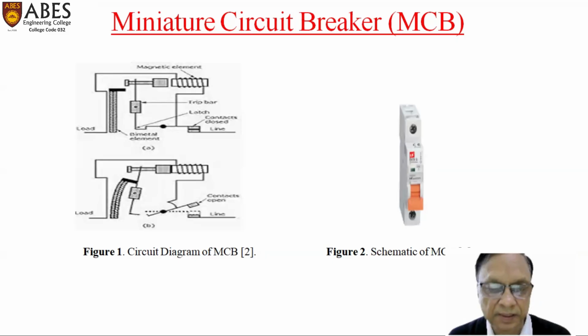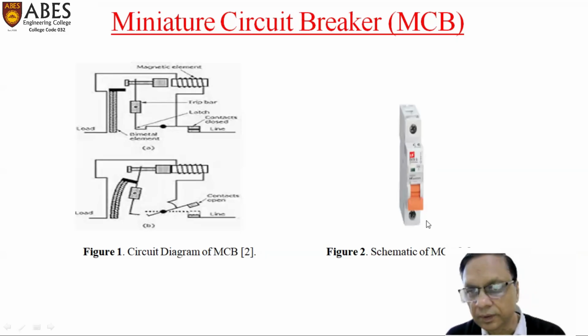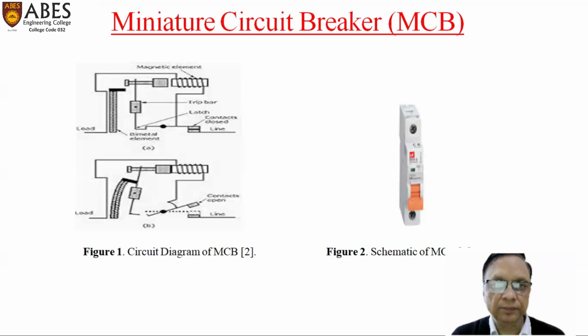MCB is basically a very small circuit breaker, and we can see it here. This is an MCB, and here it is of 5 amperes rating. It is a small rating, so here we don't have a large capacity. MCB is the lowest level after the fuse. After the fuse, the next level of switchgear is the miniature circuit breaker.